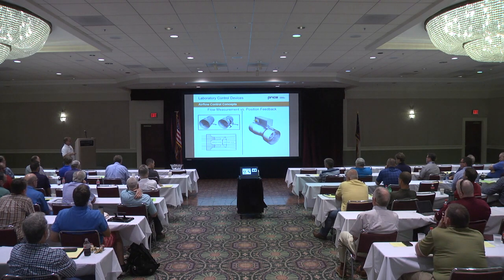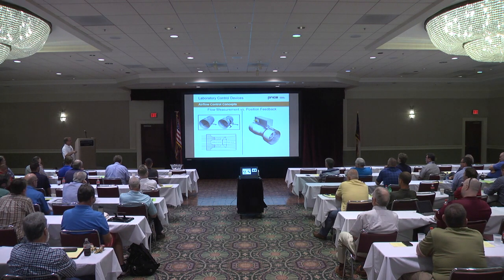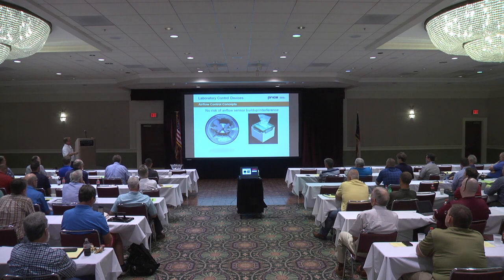But cross flow sensors are going to get clogged by whatever comes through that duct. Vortex shedding devices aren't as bad, but they do have removable plates on those devices too, for the same reason. The Venturi valve with no flow measuring devices doesn't have the need for cleaning. So there's an example of buildup on a cross flow sensor. That's showing a chem wipe. That's a device that could be sucked up in a fume hood.